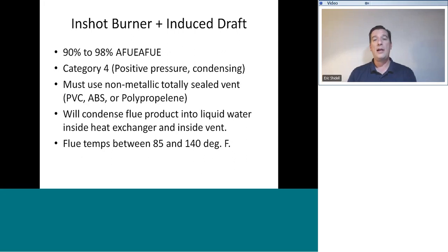When that appliance is induced draft with the in-shot burners and is a 90 to 98% AFUE, that appliance becomes a Category 4. Category 4 means that it is a positive pressure in the vent. It is blowing through the vent. It is a condensing appliance. These must use a non-metallic, totally sealed vent, such as PVC or ABS or the new polypropylene vent material.